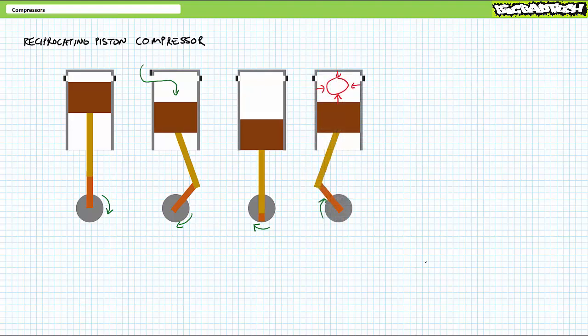The upstroke or compression phase is essentially the same, only in reverse. The crankshaft and connecting rod translates the rotational movement of the prime mover shaft into upward linear vertical movement pushing the piston up. During a majority of the upstroke, both the inlet valve and outlet valve remain closed. As the piston ascends, volume in the barrel decreases and pressure increases. At a certain point, the outlet valve opens and expels the compressed air into the pneumatic system. The compression phase ends, the outlet valve closes, and the inlet valve opens, ready to begin another suction phase.